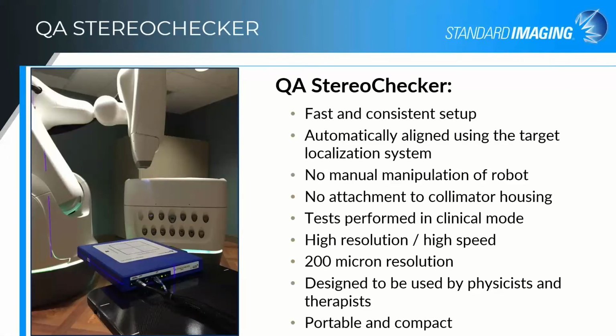It's currently primarily designed for use with the CyberKnife system. There was a pretty strong need there for much more robust and fast QA because of the length of time that is required if you're using film for all of the daily measurements that you're supposed to be doing. We found in talking with a lot of users that they didn't have the time to do the several hours worth of QA every day. And therefore, a lot of the QA was not being done quite as frequently as was recommended.